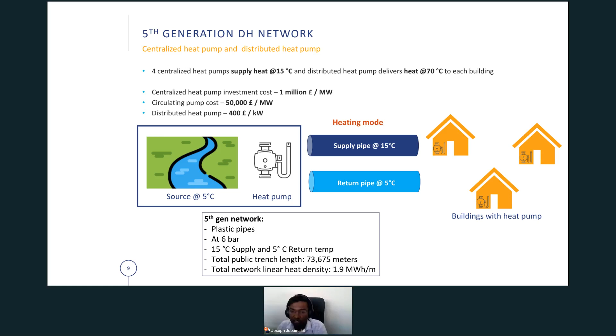So here in the 5th generation system, we have plastic pipes at 6 bar pressure, and then we have supply and return temperature of 15 and 5 degrees Celsius. And then for the distributed heat pump, we used 400 pounds per kilowatt. That's the cost we used for the distributed heat pumps. So now let's compare the design scenarios. First we have the 4th generation design, and then for the 5th generation design of the Ambient Loop Networks, we provided the COP for the heat pump, with simulations at a COP of 2.5 and a COP of 3.5.